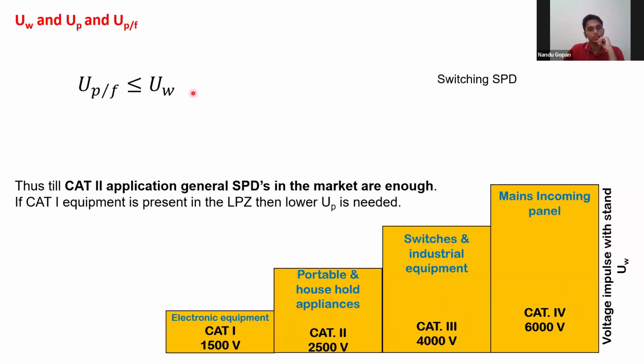This UW is this 4000 volt, 6000 volt, or 2.5 kV. UW means voltage impulse withstand. So this much impulse voltage, the equipment can withstand. That is what UW means. So if I have a computer and this computer can withstand 2.5 kV of impulse, that is what it means. So there is a formula: UP by F should be less than UW.